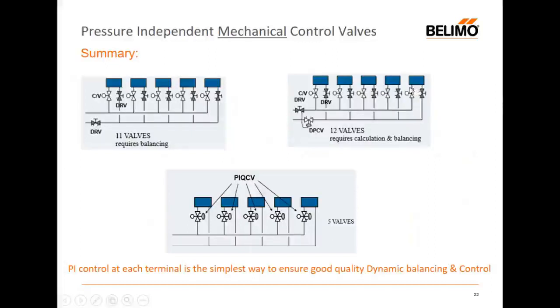So if I size that with 20 kPa, my valve authority is below 0.25, it'll go to 0.2. So there is a risk that if I don't make very careful selections and quite high resistances actually, then I'm going to lose authority quite quickly, even though I'm controlling the pressure to each branch. And I'll need 12 valves, and I'll need to balance them, and I'll need to do a fair bit of calculation.